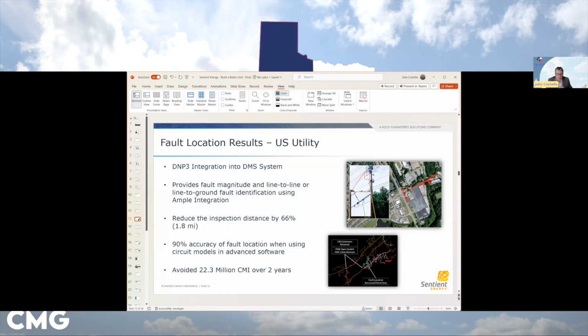Gary Ayer, who's on the line, likes to use the phrase fast time to value. Essentially, for sensors, you can put them up with a hot stick. You don't have to take an outage to do so. You can put them on the lines while they're live. And once you deploy this, they can be up and running in a matter of days. It takes approximately 15 to 20 minutes to install a triplet. That would be 3 sensors, 1 on each phase.